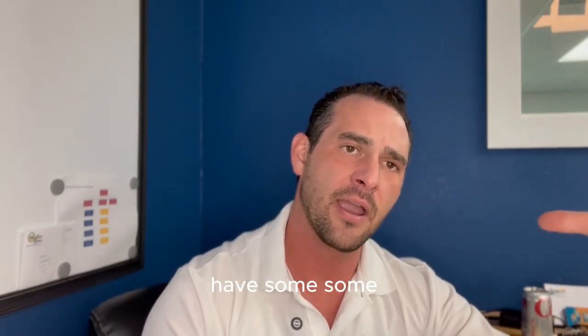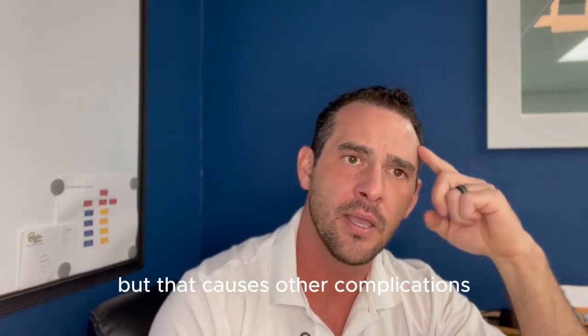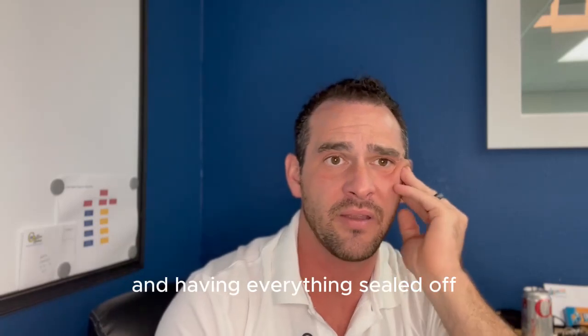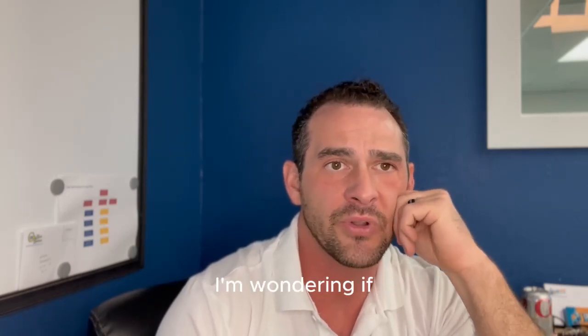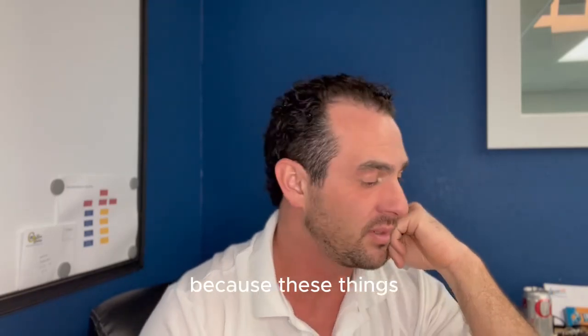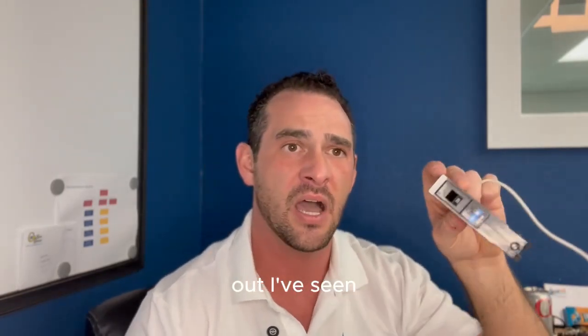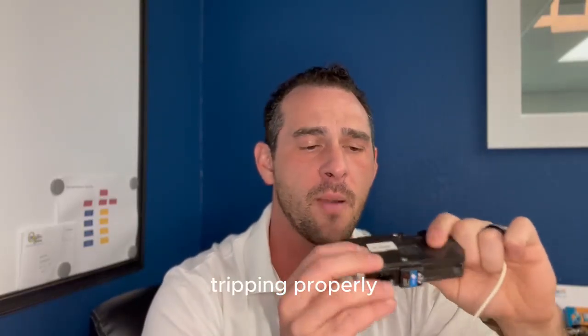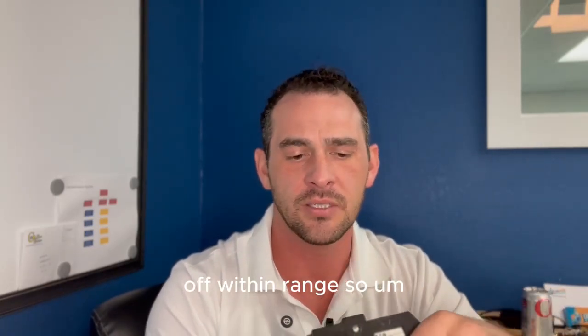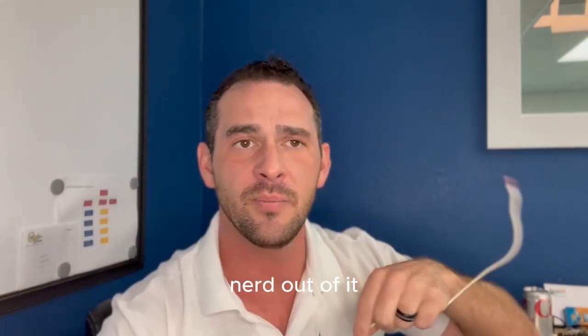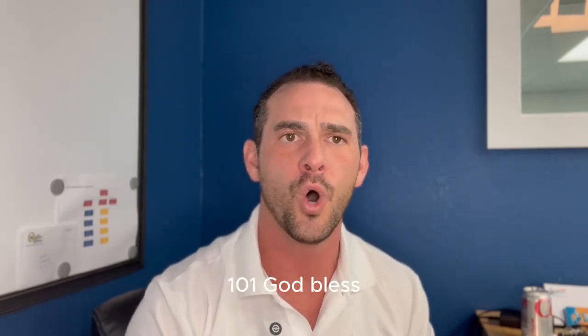At some point, it'd be cool if these circuit breaker boxes could have some air cooling units inside of it, but that causes other complications with fire protection and having everything sealed off. But it would be cool. Industrial cabinets, they have cooling fans inside of them, so I'm wondering if down the road that's going to be something they'll go to just to keep the temperatures down, because these run hot and they go out. I've seen 3-4-year-old arc fault breakers that weren't tripping properly. When you tested it, it would slowly kick off. You would test the milliamps that it would trip off. It wouldn't trip off within range. So there's definitely a lot of room for improvement when it comes to arc fault protection. But there you go. So we're going to nerd out a bit. There's a little arc fault, ground fault 101. God bless.